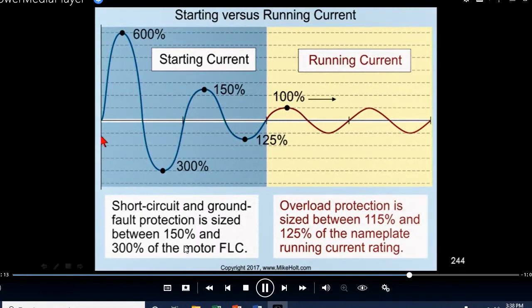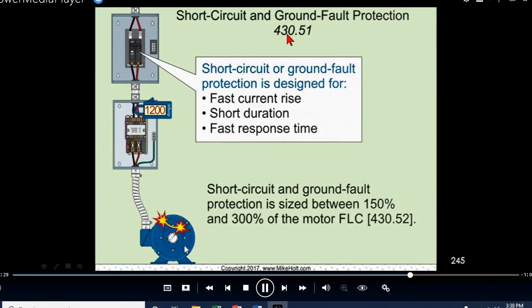When a motor starts, it starts at a high inrush current, and then as time goes by, it starts getting into the running. So you have starting currents and you have running currents. So we have to have a protection device that would allow the motor to start, but then we have to be able to protect the motor to make sure that there's not an overload condition. We do that by sizing the short circuit ground fault protection up here to allow this motor to start.